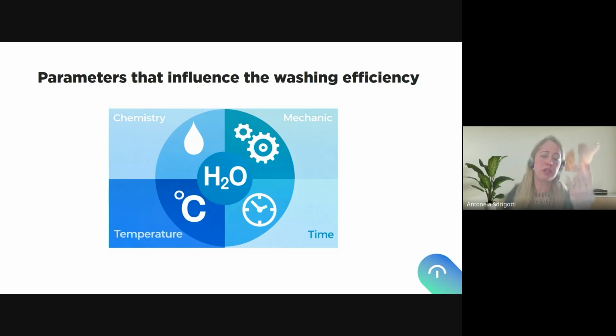And of course, last but not least, the time. We have to validate the time we are going to spend to clean different types of loads, because not all of them are cleaned with the same difficulty. And also, which is not here, one other parameter that influences the outcome is the load. Do not overload the chamber because we are in a hurry, because that will be very detrimental for the efficiency of that washing.